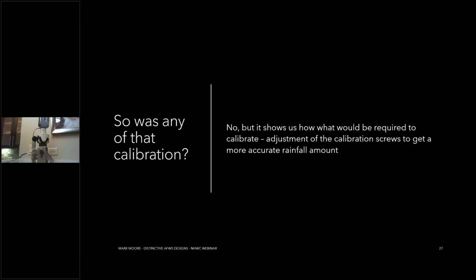Typically with flood warning systems, you're going out every 6 months or so just because those funnels are going to clog. And those funnels are going to clog with leaves or bird poop or dust, construction debris. And if you're out there cleaning tipping bucket funnels and cleaning the screens and keeping everything neat and orderly anyway, it's a good time to go ahead and do a calibration. So generally speaking, my recommendation is dynamic calibration every 6 months, static calibration anytime you bring the tipping bucket in from the field. Again, I don't really think there's a lot of worth in doing static calibration in the field because there are just too many other factors that are going to make that bucket tip too soon. That's a test bench only thing. Now, there might be some agencies that want to calibrate before a monsoon season or before a hurricane season, but that still typically falls within about an every 6 month period. Thanks, Ben.